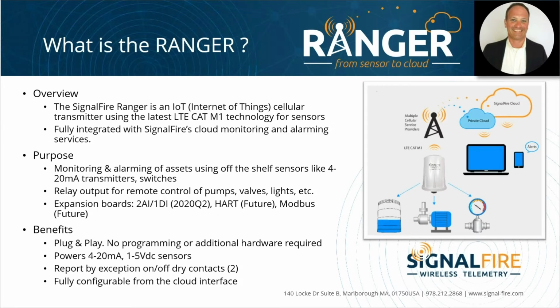It can connect to multiple types of I/O: analog, with 1 to 5 volt or 4 to 20 signals, and digitals where you can put on-off switches. There's also an output on the unit that can send a relay output to control pumps, valves, or lights. We also have an expansion board slot, and we have plans to add more I/O, along with HART and Modbus support. Within our server, we can fully configure it. On the digitals, it can report by exception whenever there's a change of state, and for all other data, we have a check-in interval ranging from 1 minute to 60 minutes. Go ahead and click next.